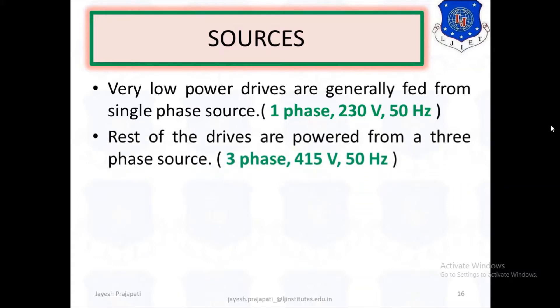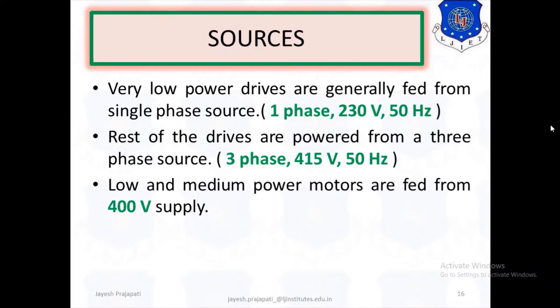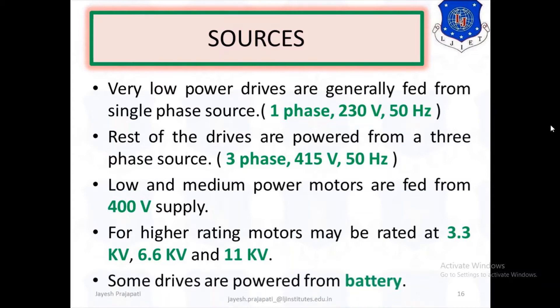The source may be AC supply or DC supply. AC supply can be single-phase or three-phase. Very low power drives are generally fed from single-phase sources at 230V, 50Hz. The rest of the drives are powered from three-phase sources at 415V, 50Hz. Low and medium power motors are fed from 400V supply, while higher rating motors may be rated at 3.3kV, 6.6kV, or 11kV.